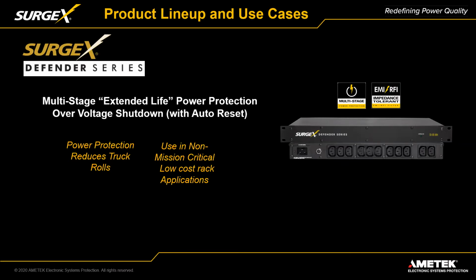With the Defender series, we're able to offer very reasonably priced surge protection. It's not quite surge elimination, so it's for lower price racks, the non-mission critical stuff. When you're up against a bid for a very low end device, you can say, instead of using that MOV-based product that will wear out in 6 months, let's put this Defender on here. It's actually a quite novel use of MOVs and gas tubes to provide that kind of protection.